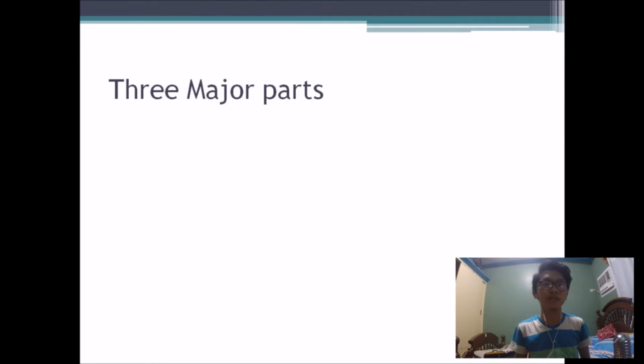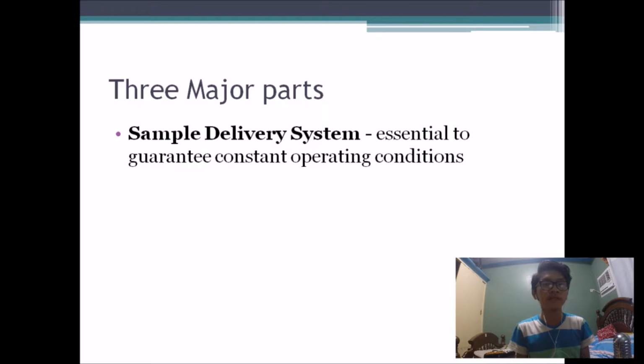The three major parts of the working principle of the electronic nose are, first, the sample delivery system. The sample delivery system enables the generation of the headspace, or the volatile compounds of a sample, which is the fraction analyzed. The system then injects this headspace into the detection system of the electronic nose. The sample delivery system is essential to guarantee constant operating conditions.